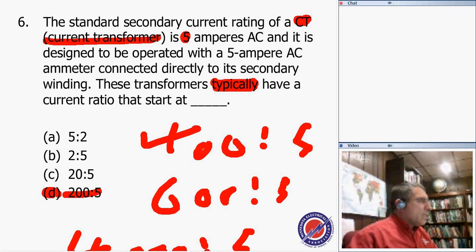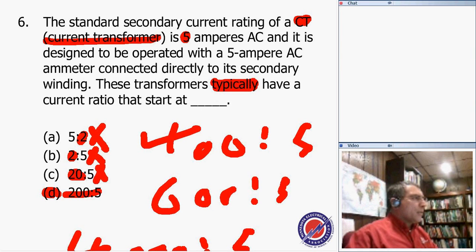So why is this one wrong? Because first, the secondary has to be 5. Why is this wrong? Because it's very small, 2 to 5. I mean, you really want to measure 2 amps? What about this one? It's also too low. Look at the 20 amps, it's low. So 100 is high, and good, because 200 amps is the threshold.